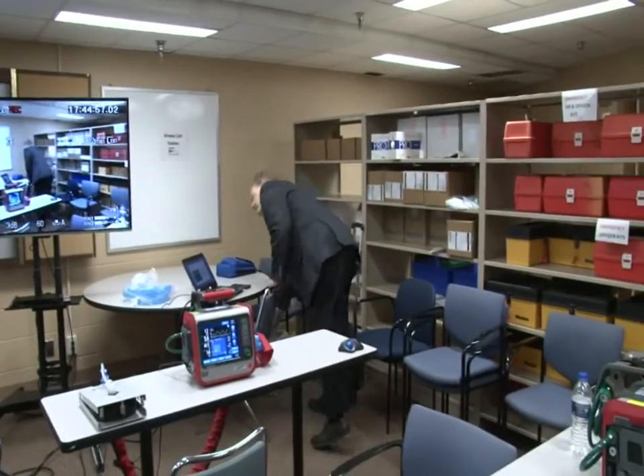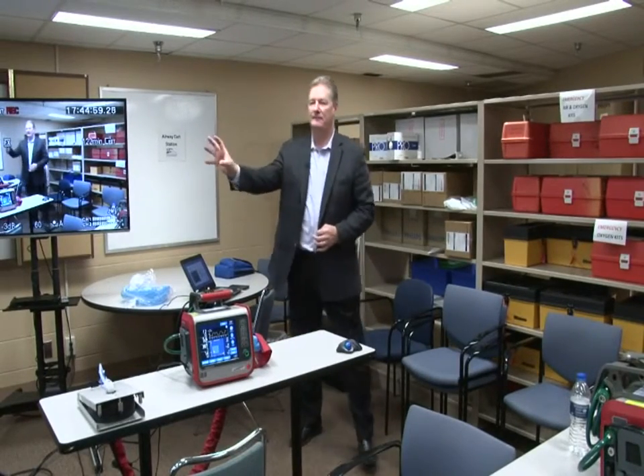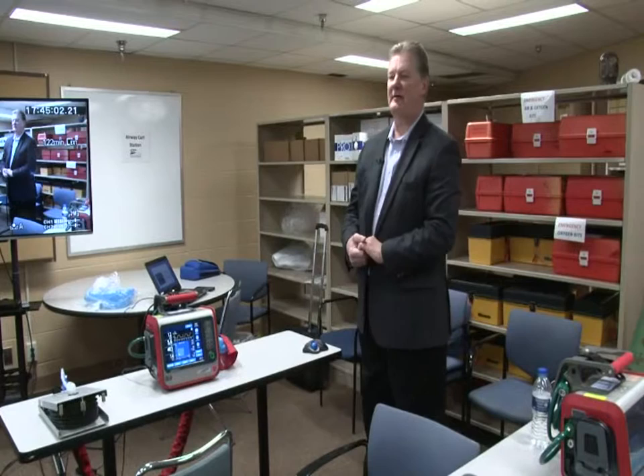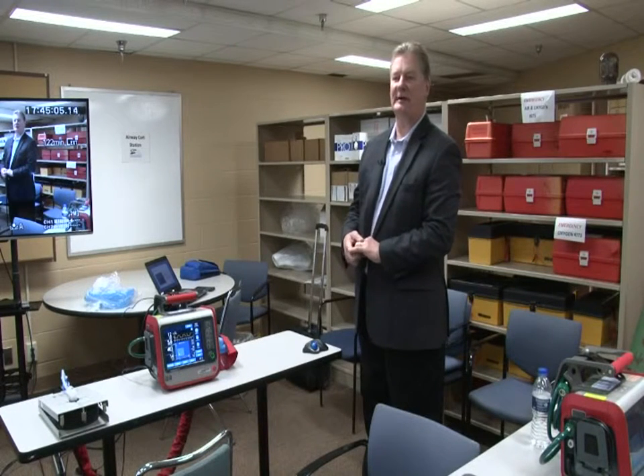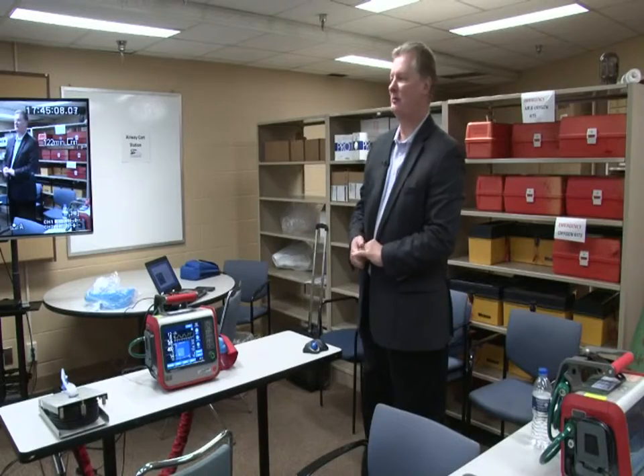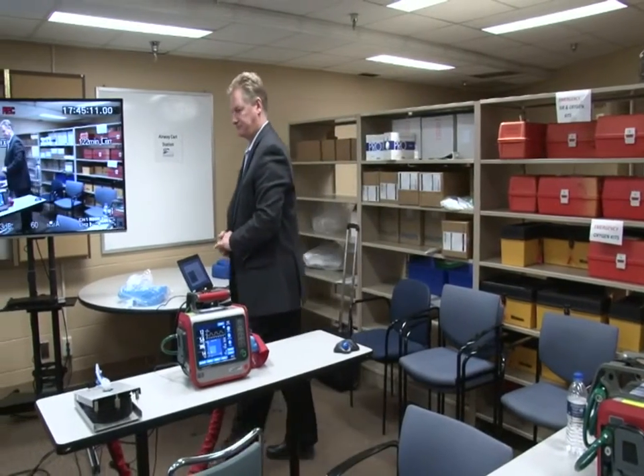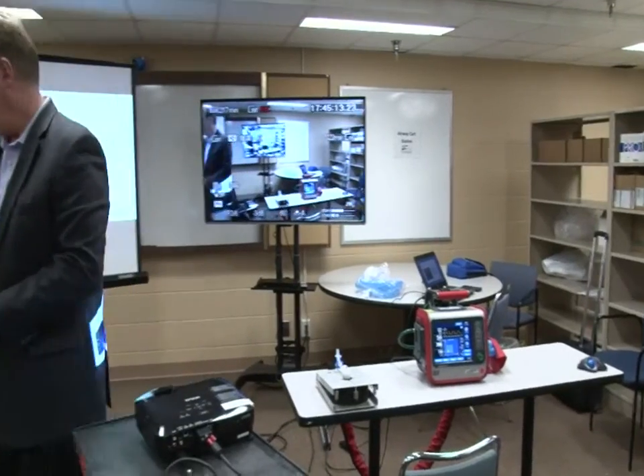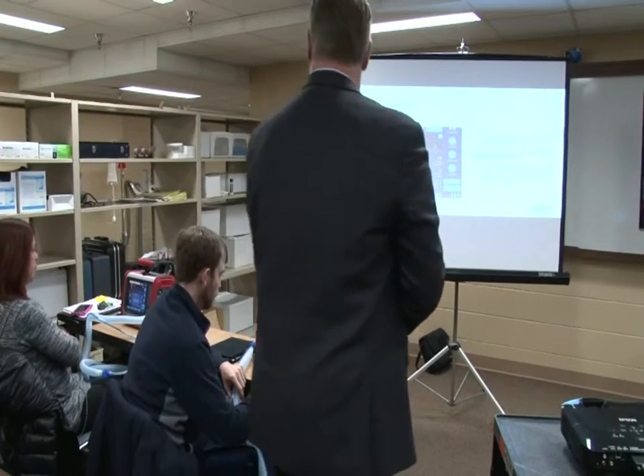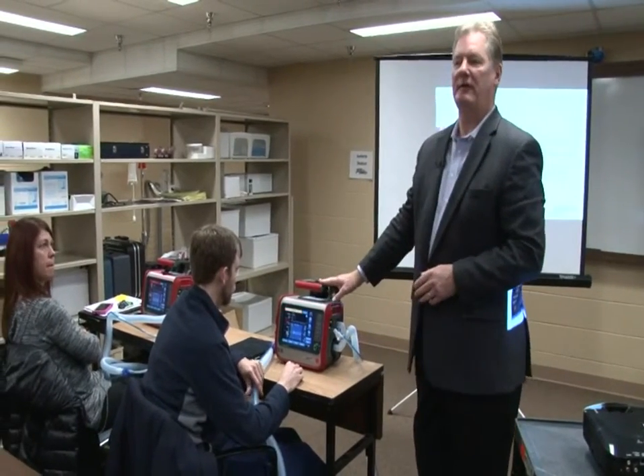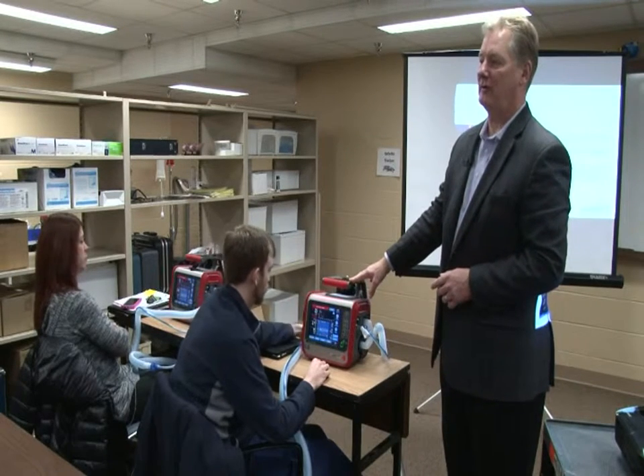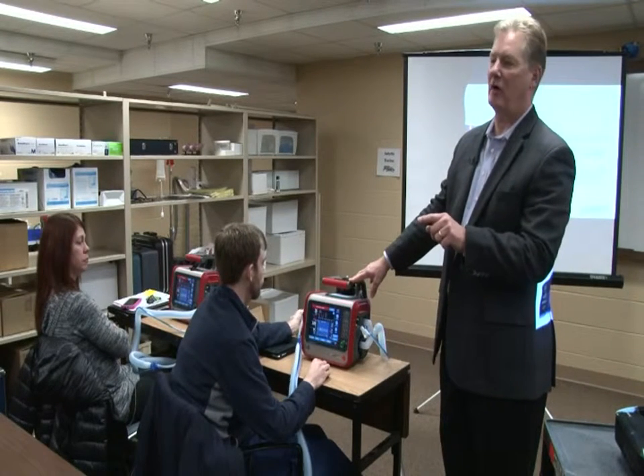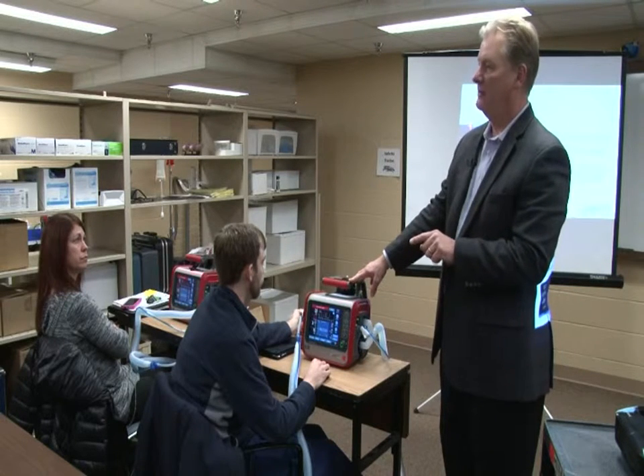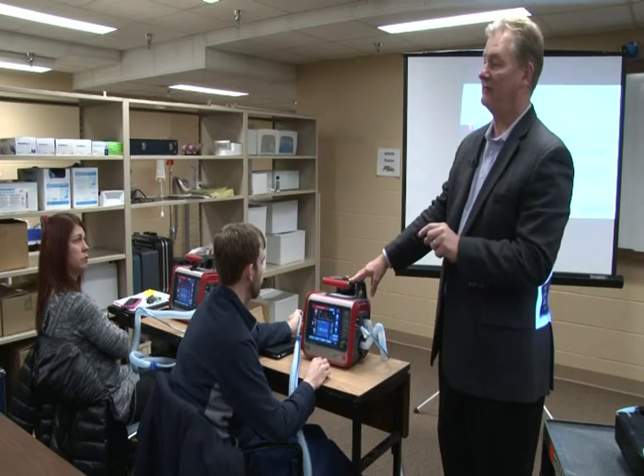Okay, did everybody notice that when they first turned the ventilator on and started it, the ASV graph didn't have any red box, it didn't have any numbers on it, and now it has a red box and it has some numbers on it. Okay? Let's see why you guys are alarming here. That's okay, that'll correct itself. Those will all go away. So as you see on these ventilators, there are some alarms when you first turn the ventilator on, but when you first press start, the ventilator automatically activates the alarm silence button for half of the normal time, which is 2 minutes. It activates it for 1 minute.